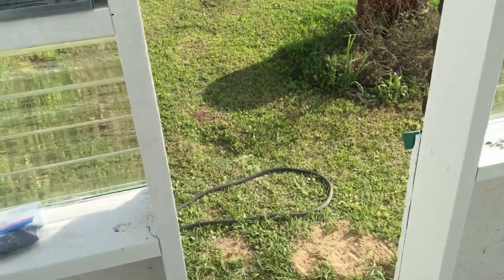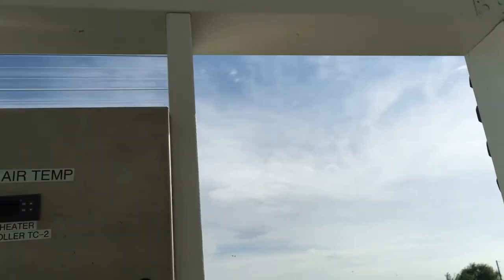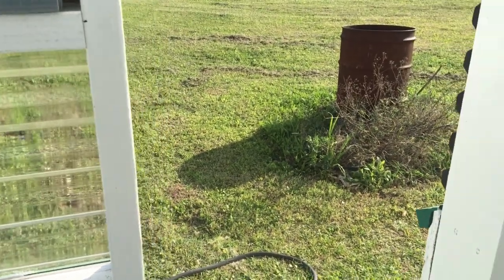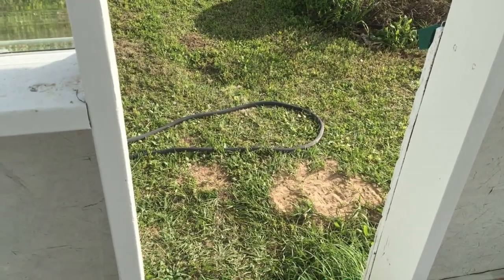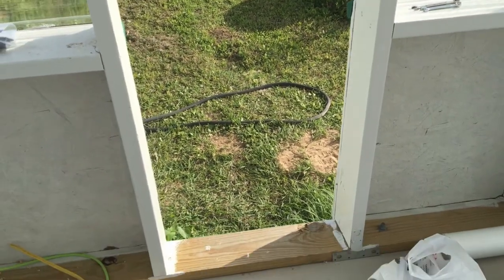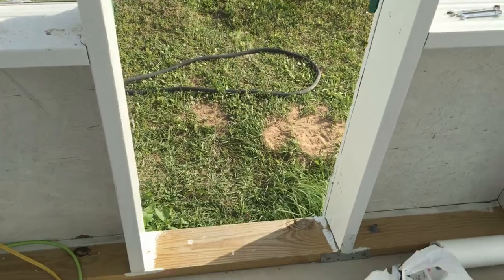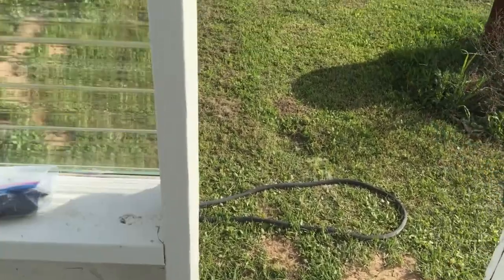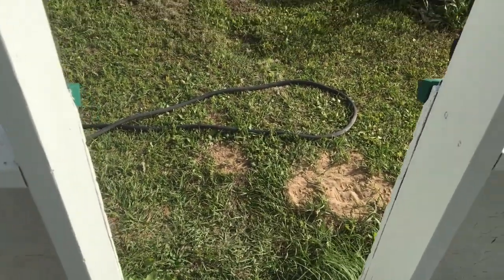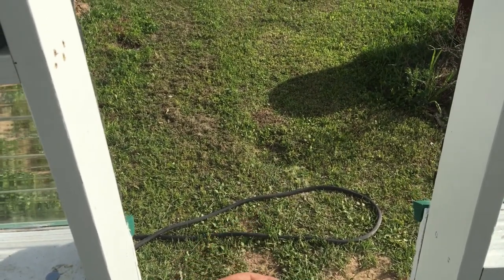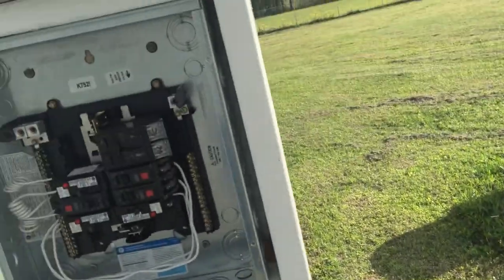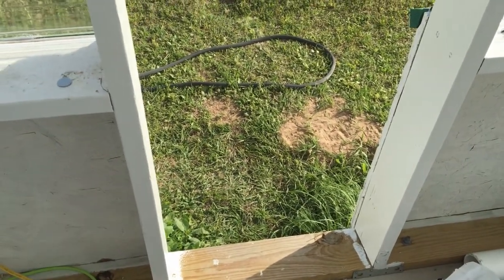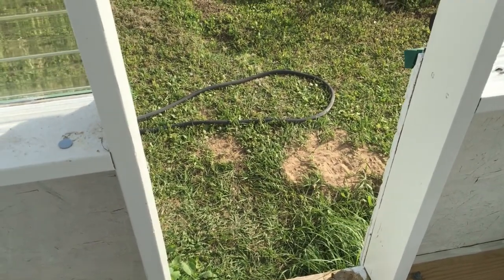So the evap cooler is going to be 6 feet from the top to right about there. Down here, I've got a couple of heat exchangers coming. And when you want to run the heater, you'll close a damper out here that will seal off the evap coolers. This will be sealed off. So then air will come in from the floor. The air will come in off the floor, go through that heat exchanger, and then come up and out the fans.